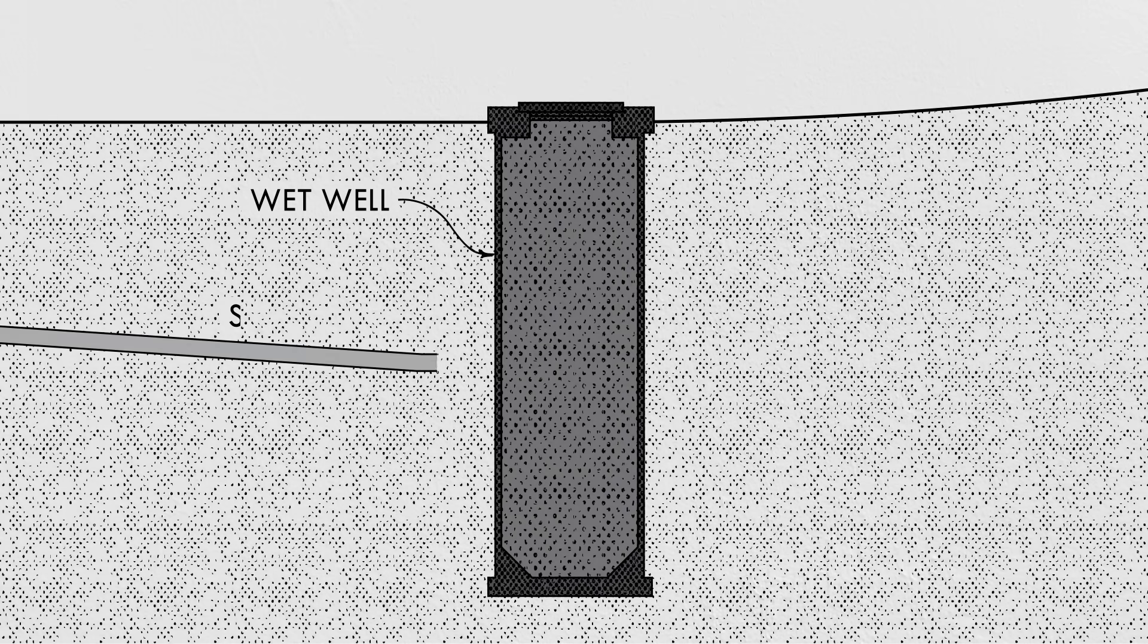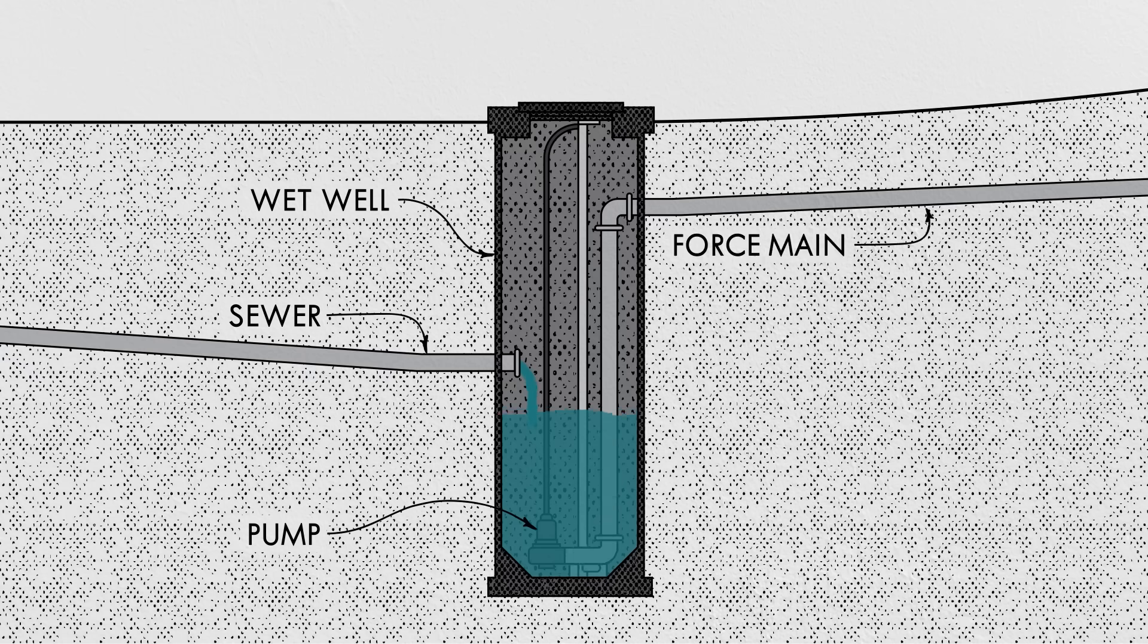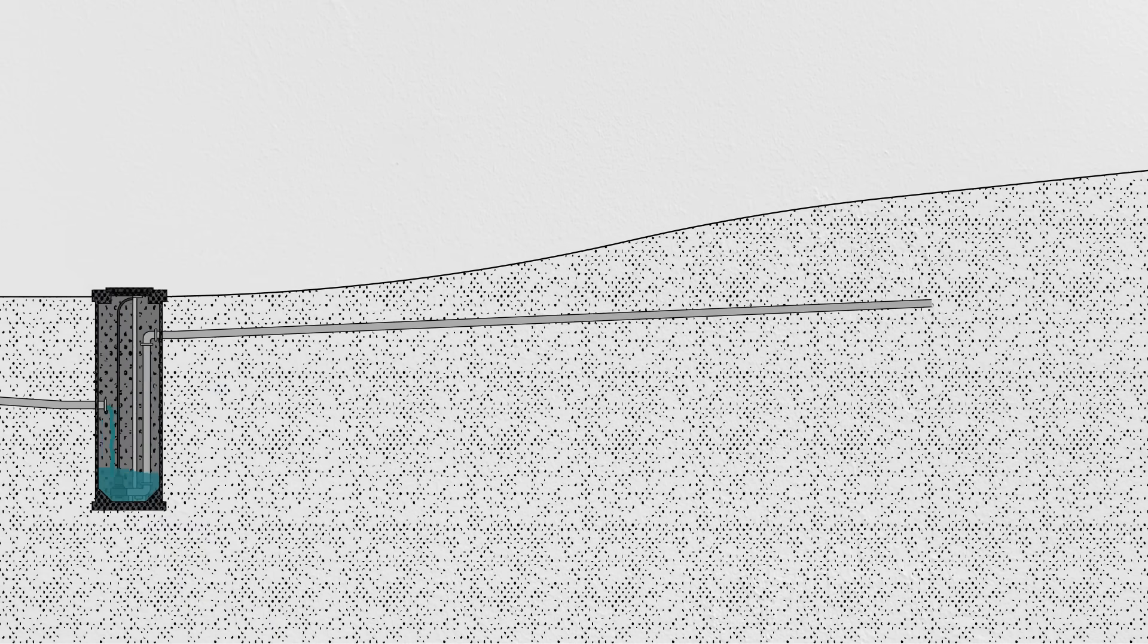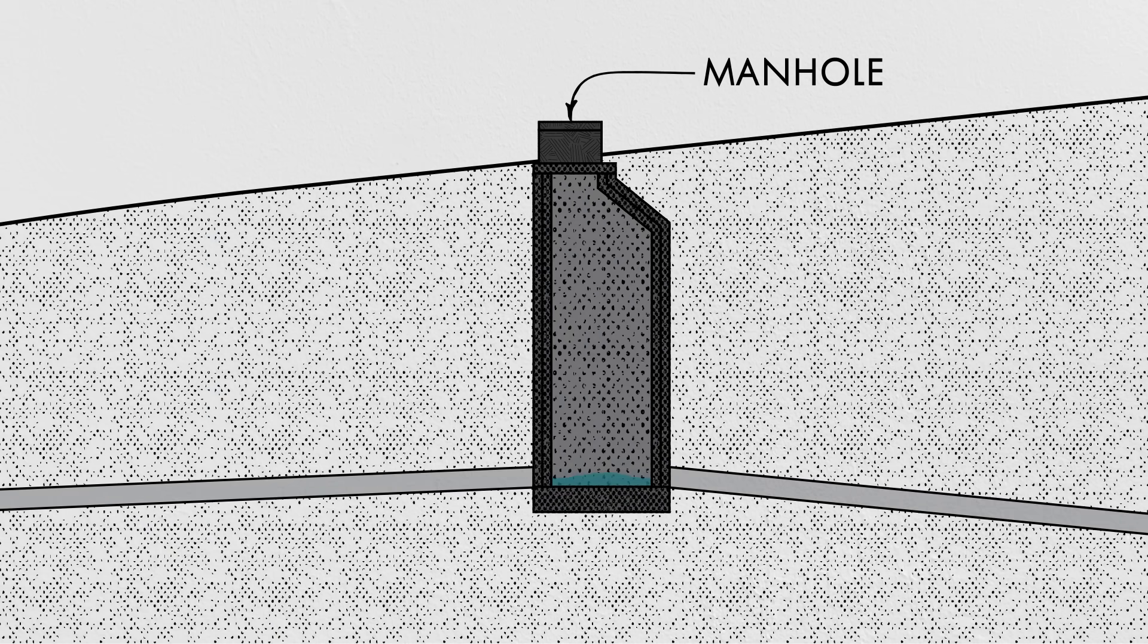A typical lift station consists of a concrete chamber called a wet well. Sewage flows into the wet well by gravity, filling it over time. Once the sewage reaches a prescribed depth, a pump turns on, pushing the wastewater into a specialized sewer pipe called a force main. You always want to keep the liquid moving swiftly in pipes to avoid the solids settling out, so this intermittent operation makes sure that there are no slow trickles during off-peak hours. The sewage travels under pressure within the force main to an uphill manhole, where it can continue its journey downward via gravity once again.